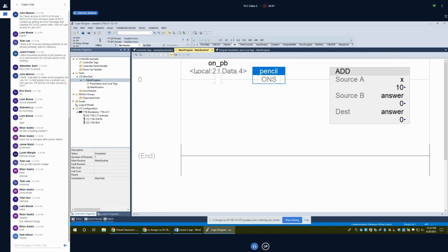And then you're going to come back up here, the next scan, and you're going to go, you're already a 1. And so you're going to jump to the next instruction. And this next instruction, they're going to say, oh, this is a one-shot. And it's a 1. So it's going to put up a wall here and block all logic past it. So it's only going to allow this instruction to be executed once, regardless of how long the instruction that precedes it is true.